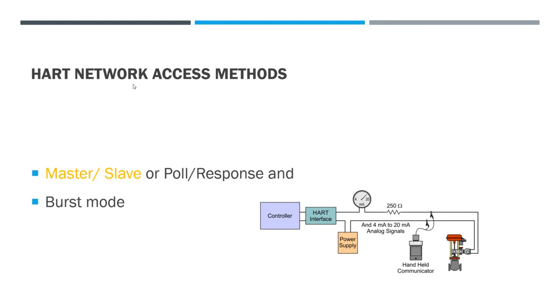Speaking specifically to HART network access, HART is typically a master-slave, or sometimes called poll-response, system. The master says, 'hey, I want to know what your PV is,' and you, as a transmitter, respond back. If I don't ask you, you don't respond — so it's good that way.